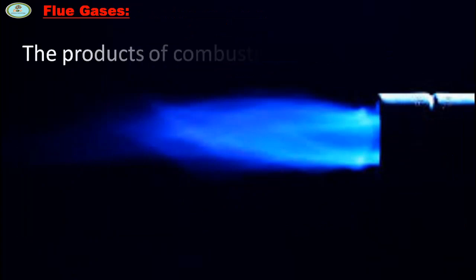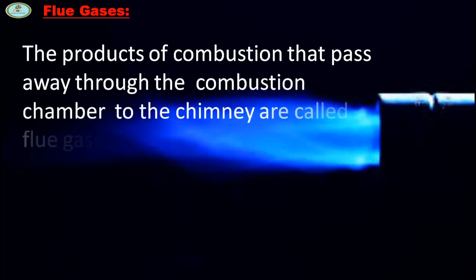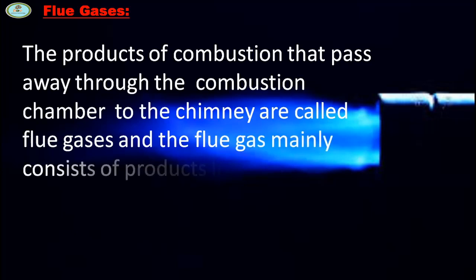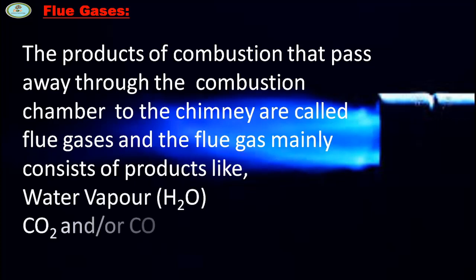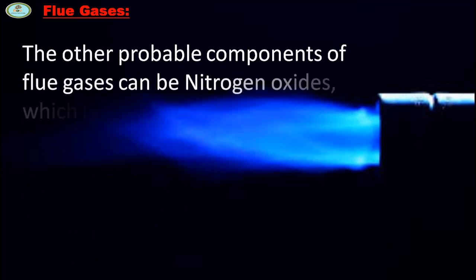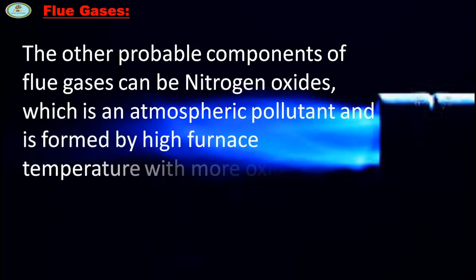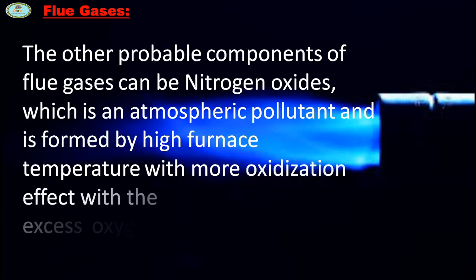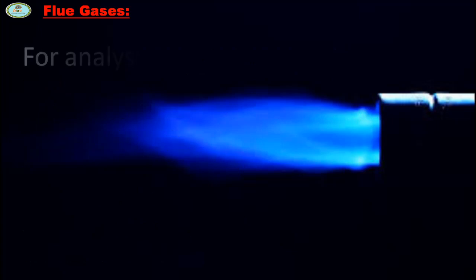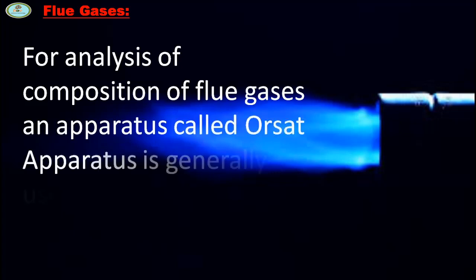The products of combustion that pass away through the combustion chamber to the chimney are called flue gases. The flue gas mainly consists of products like water vapor, CO2 and CO, and nitrogen. The other probable components of flue gases can be nitrogen oxide, which is an atmospheric pollutant and is formed by high furnace temperature with more oxidation effect with the excess oxygen supplied with combustion air. For analysis of composition of flue gases, an apparatus called Orsat apparatus is generally used in boilers.